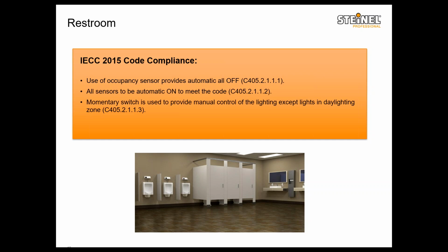And again, I'm not seeing this quite often in schools, that there is some form of momentary override switch for the restrooms, but the code requires it. I don't see it much in designs nowadays that anyone is asking for a momentary switch in restrooms in schools.